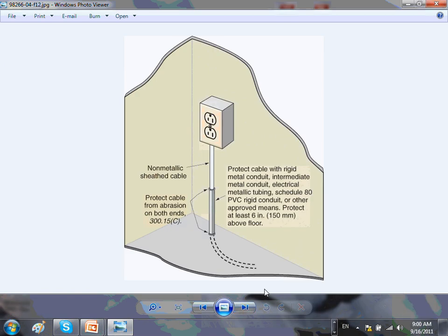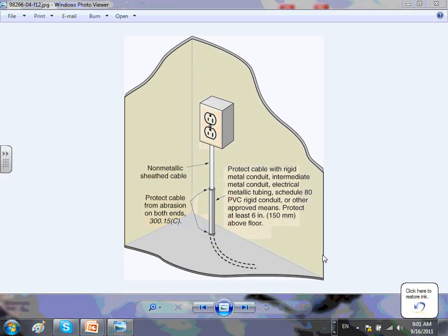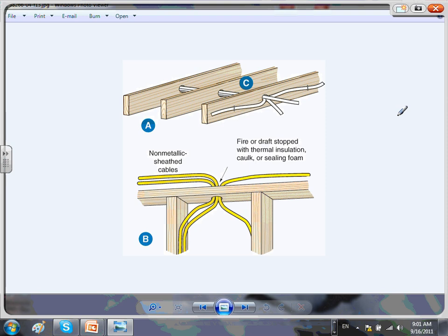When using Romex, you have to protect it from physical damage. If coming from the basement exposed, you're supposed to put it in a PVC or EMT conduit. This happens in basements a lot — as you drop from the ceiling going to outlets against the block wall, you have to put them on EMT. If you caulk the area because of thermal insulation sealing, then you have to derate. You have to derate because of trapped heat.